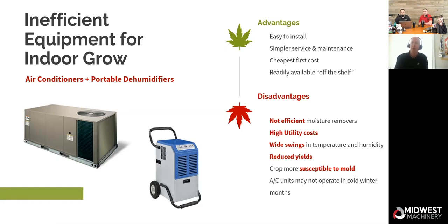So you have to look at what you're trying to accomplish. If you're going to throw these into your money room, which is your flower room, and that's also the high latent load, is that the right product for you? And then we start talking about these portables. Most of the portable units that people are using these days reject their heat to the space. What I mean by that is, if a unit takes 75 degree air into it to remove moisture, the leaving air temperature will probably be about 95. So now you're putting heat back in the room from this operating unit. It's not connected to something to reject the heat from compression. The more these run, the more heat they put in a room. That becomes very inefficient because now this air conditioner has to run more frequently to keep the temperature down.